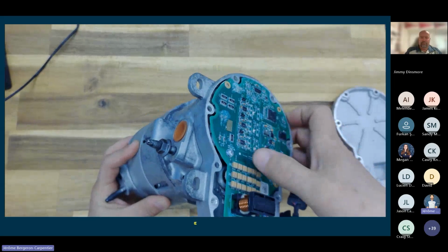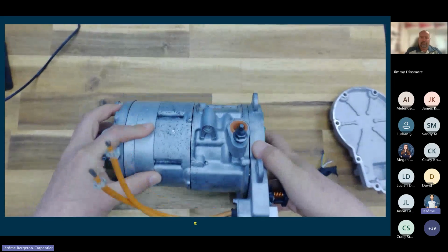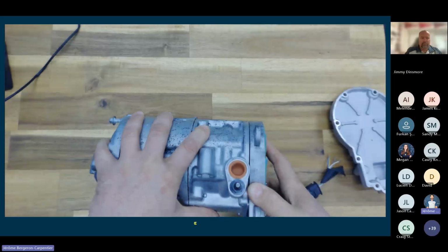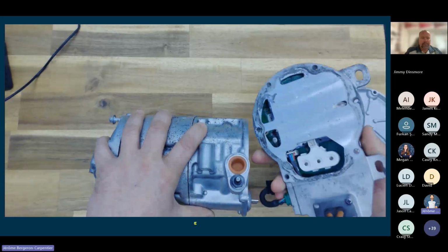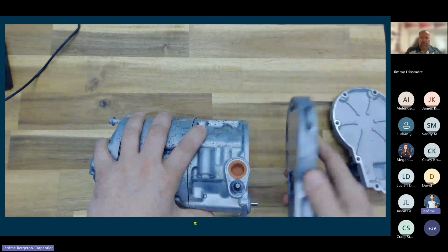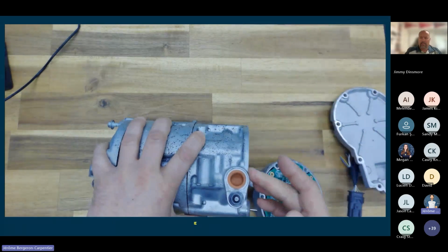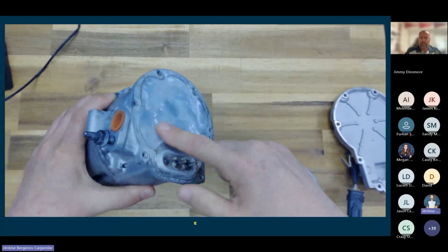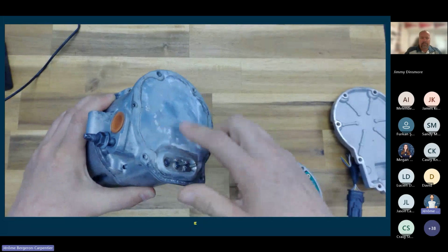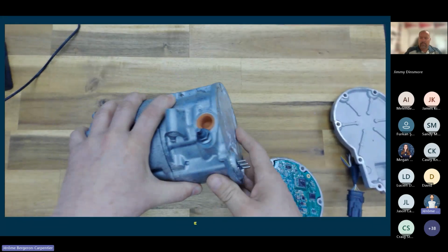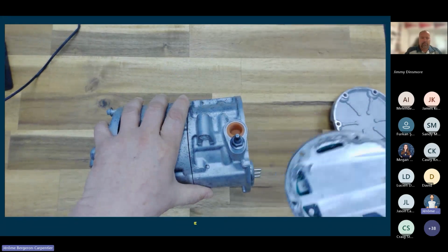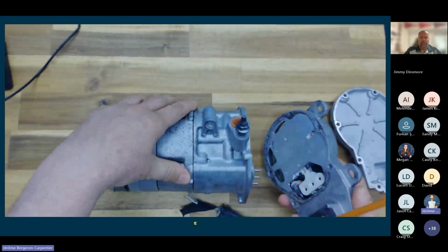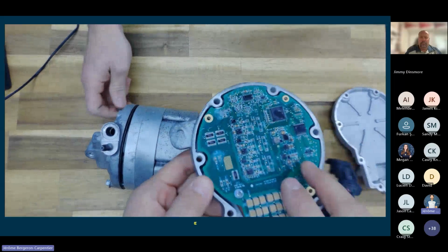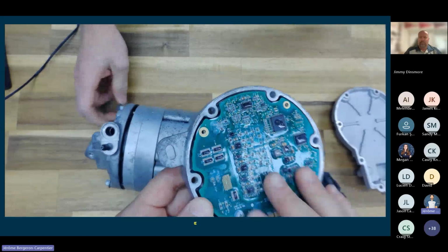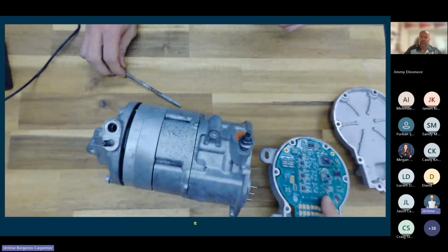I'm going to go through some of the components here, but you can see also, if I remove this from the stator, there's almost like a heat sink plate, but it runs right beside the low side port coming in, which would be very cold, carrying the heat from the evaporator. So one of the unique things you'll see in a lot of these high voltage AC compressors is the low side port is close to what we call the controller inverter, which controls this three-phase motor.